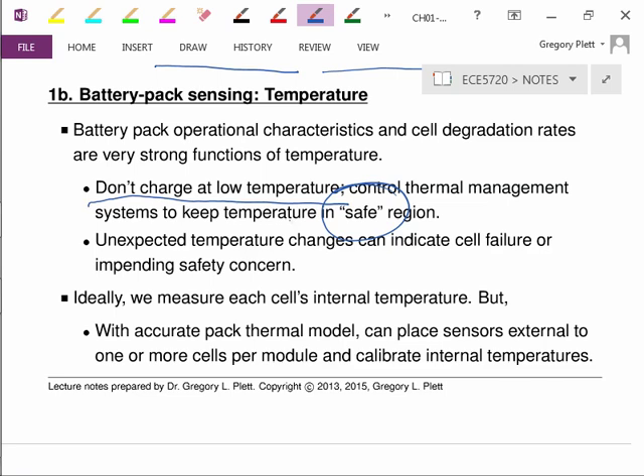Measuring temperature also allows us, in some cases, to have an indicator that something is seriously wrong, like a cell failure. If the temperature increases quite rapidly, that might indicate a short circuit or a soft short circuit inside a cell causing the increase, and I need to watch out. This isn't quite as useful as you'd hope, because usually by the time you measure the high temperature, it's already too late. But there may be situations where it's still good to know.